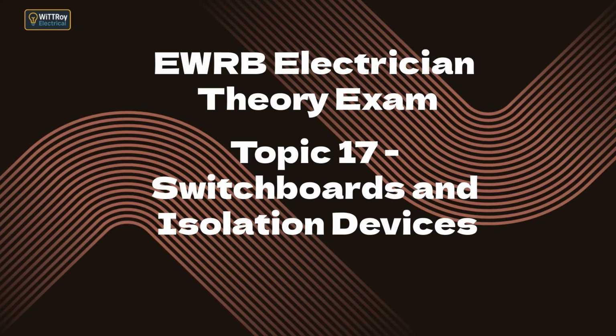17D Application of AS/NZS 3000 and earthing requirements for MEN switchboards. At MEN switchboards, AS/NZS 3000 requires very specific earthing arrangements to make sure the protection system works correctly. The MEN system relies on a single, correctly installed main earthing conductor, a main earth bar, and a main earth neutral link. This link is the connection point between the neutral bar and the earth bar, and it must be located only at the MEN switchboard unless the installation is designed otherwise under special conditions.